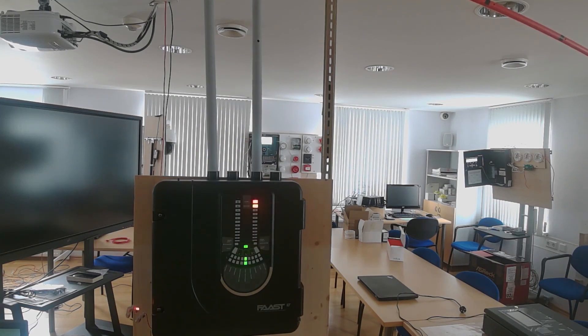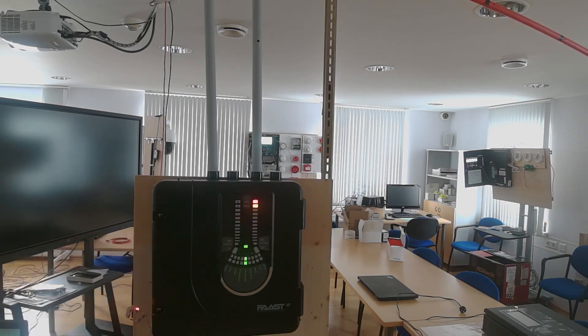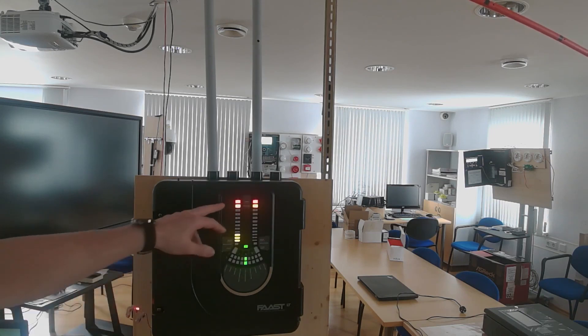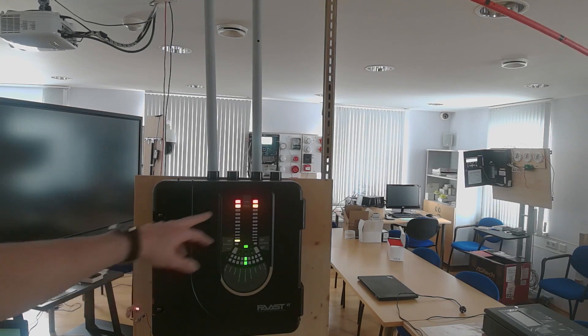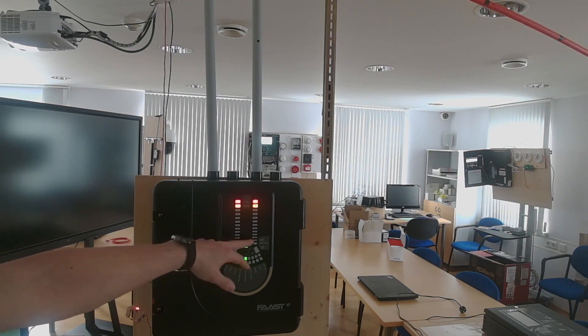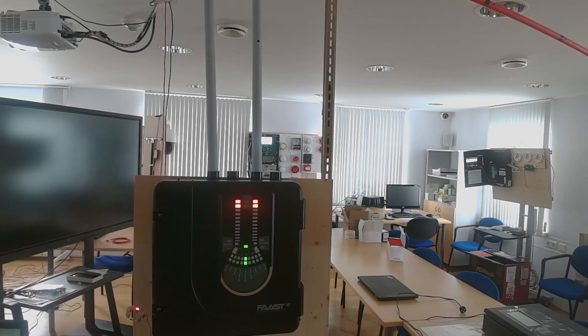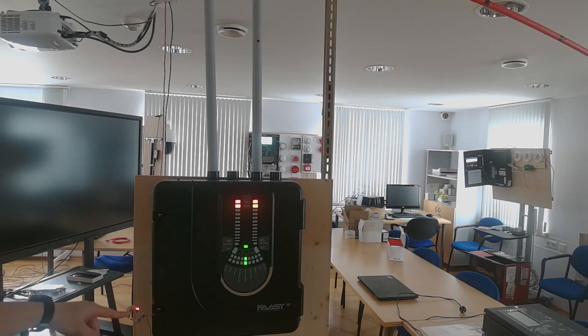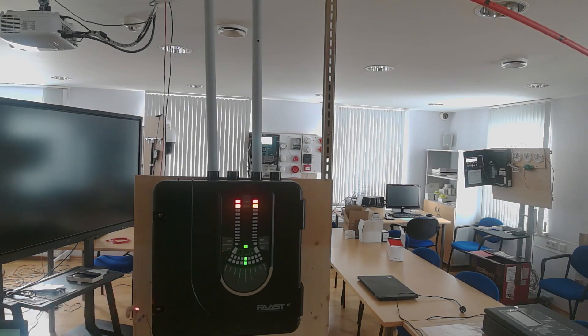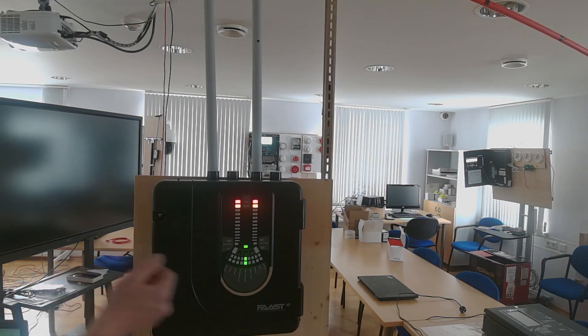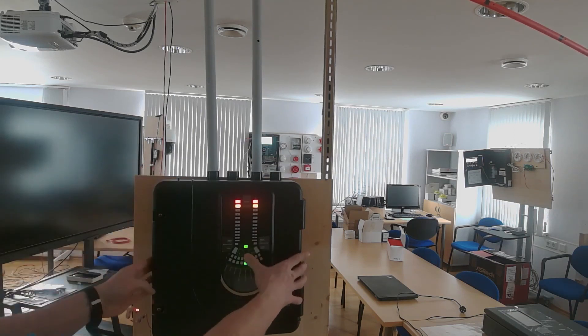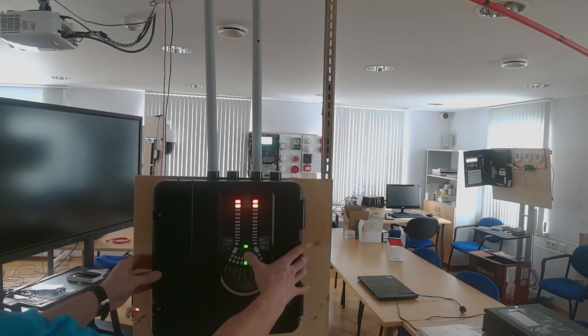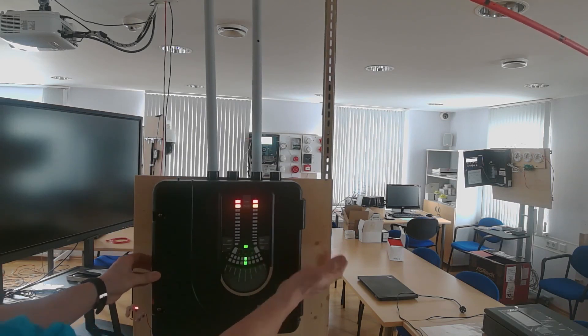You see channel two is on fire. And also some smoke got into the first channel. And it also has a fire. And it also shows the smoke level. Now the smoke level is reset. Now we can reset our device. And I also connected the bells to channel two. And it also goes on by the fire. This is in the standalone version. Now let me try to reset it.